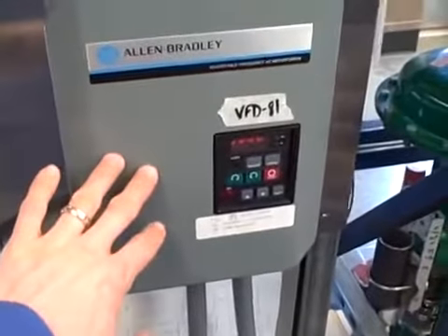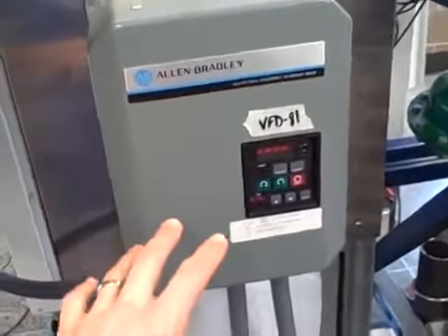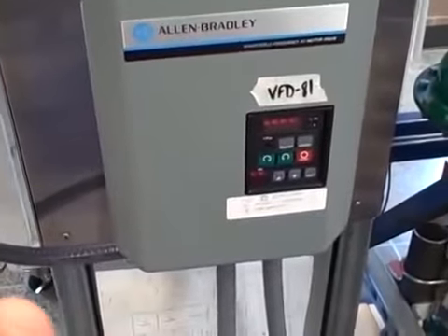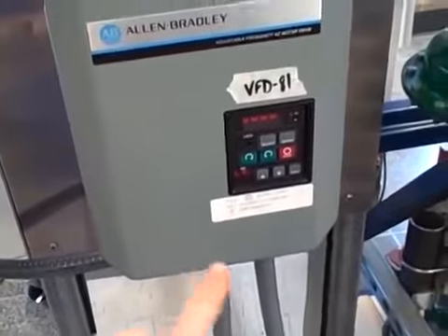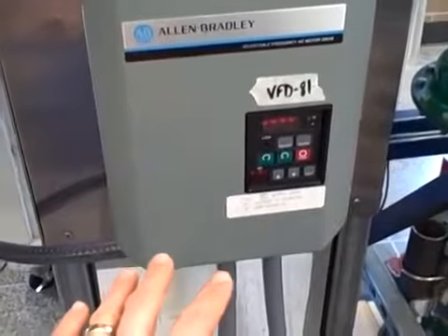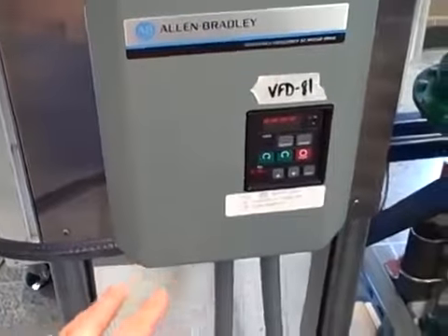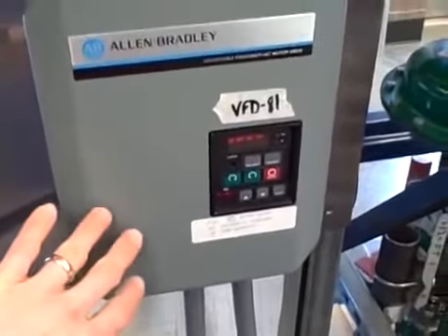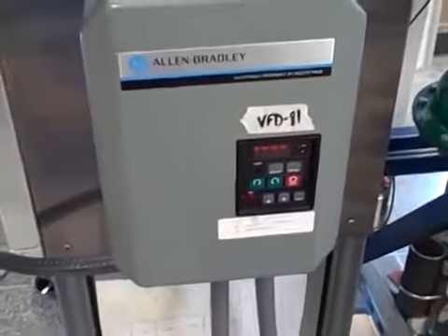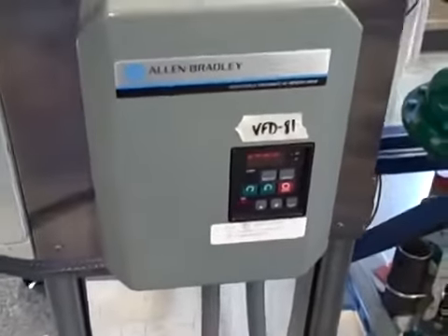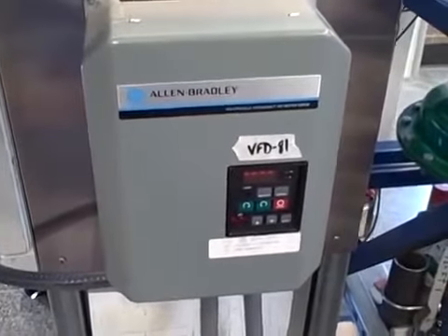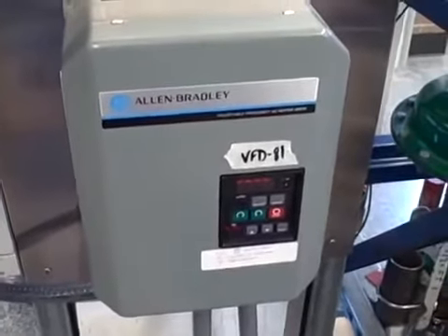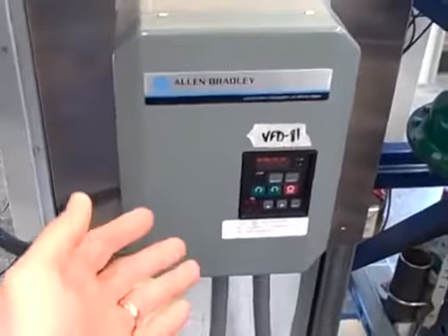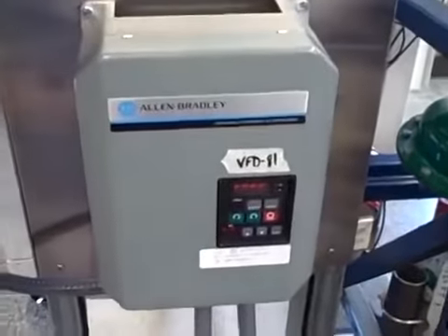So again, to illustrate, showing you a real drive, something like this Allen Bradley model, that's generating variable frequency to an induction motor. If you were to connect an instrument like that insulation tester we just saw between any one of the motor terminals and ground with the motor connected, expecting to test the motor, you're also going to be subjecting the switching transistors in this drive to very high voltages, and that will likely destroy the drive. So be aware of that, be aware of the limitations of the device, its inherent safety hazards, and know that in some cases you can actually destroy equipment it's connected to.